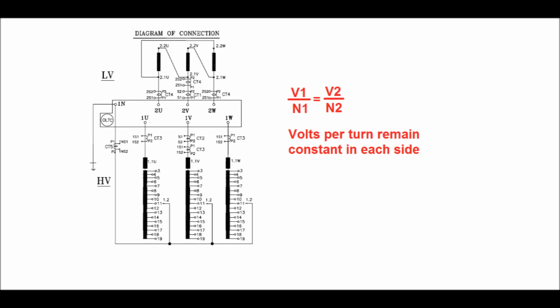not occur. So in this diagram, a 132 by 33 kV transformer winding has been shown, where the HV side is star connected and the LV side is delta connected. In the HV side, the tap winding is provided. The 1, 2 number is the selector switch position, and there exist 3 to 19 number tap positions.